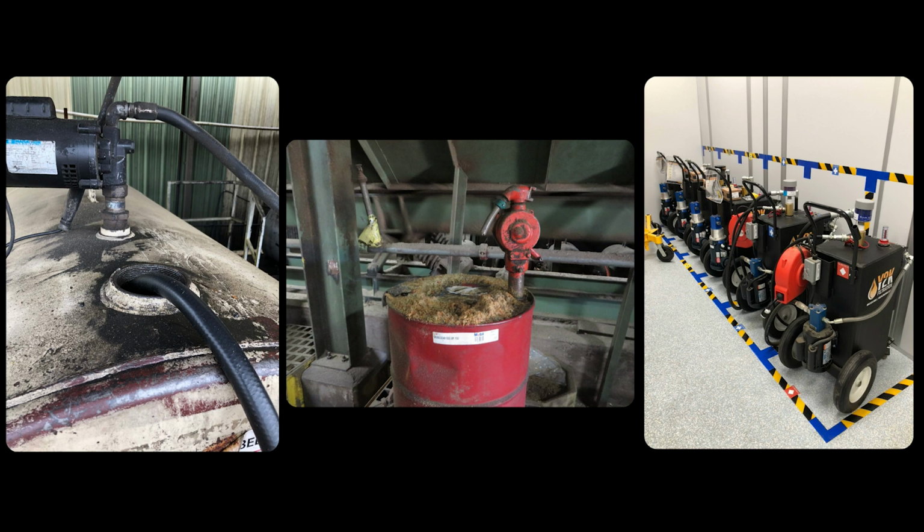More examples, and when it comes to lubrication, which is part of your prevention, in this case to the left there, you see a tank. It's actually new oil that they pump from drums, and it's standing open out there in the shed. So now you're getting moisture, you're getting dust in there. So the number one problem with lubrication many times is to keep it clean. Another example is you have a drum out in the plant there in the middle, and you're getting dust and moisture in the gear because you have no caps on there and it's not sealed. Versus to the right there, you see a nice lubrication cart with filters, caps on the hoses, and so a very nice way of keeping everything clean when you're actually adding or changing oil.